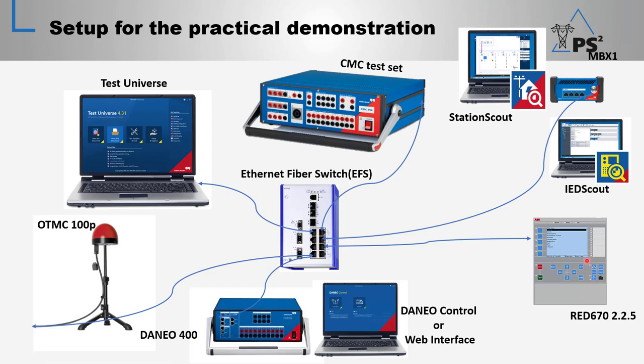And we have the IED configured with the basic non-directional overcurrent protection function, also the control function for circuit breaker open and close from the MMS client. The circuit breaker function is also used for protection tripping from the non-directional overcurrent. The IED is also configured to send the measurement values in report control blocks, and the protection start and trip information is defined in the GOOSE control block.